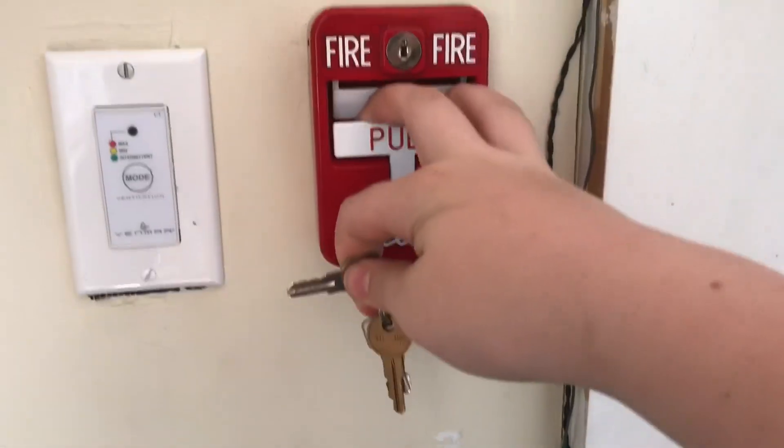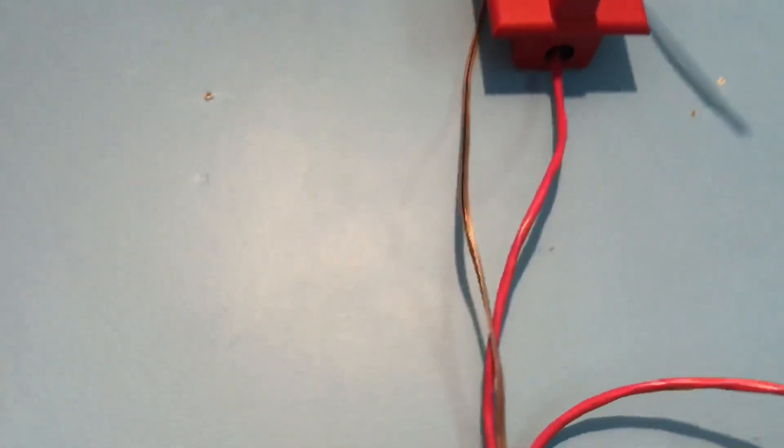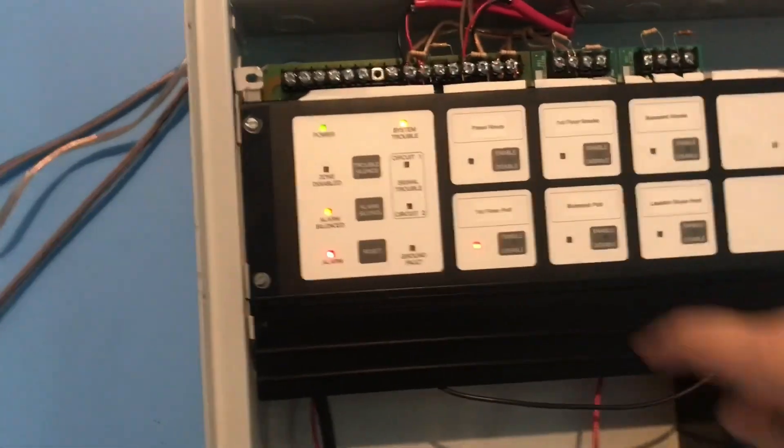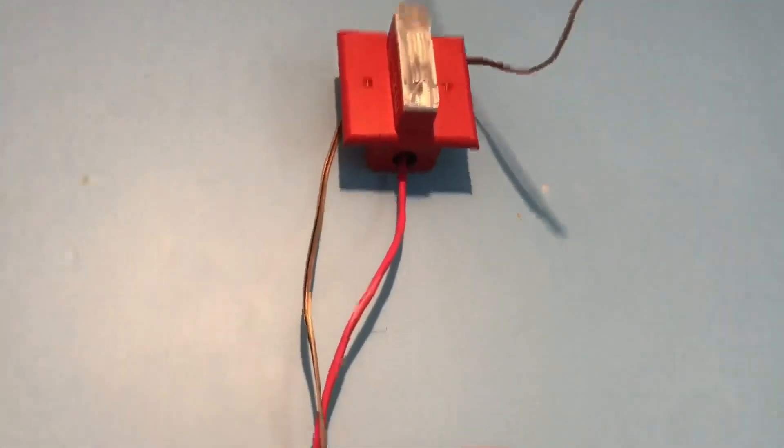So let's test them — let's do the Wheelock. Here we go. Oh, that must not be connected. And the clicking you hear is because I didn't set NAC2 to continuous — I only set NAC1, because I only have NAC1 hooked up. That's weird. I must not have hooked that up correctly, but glad we tested it.